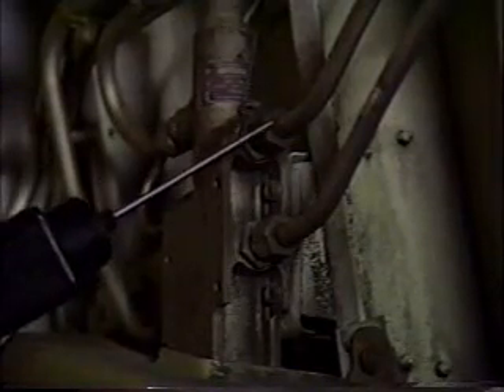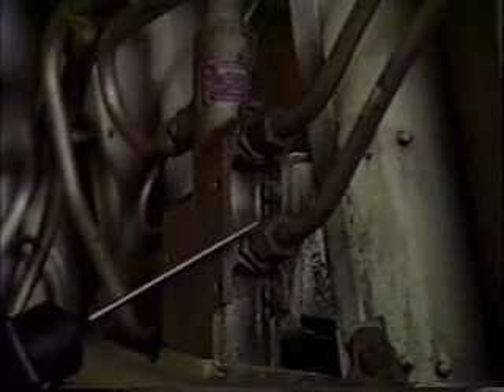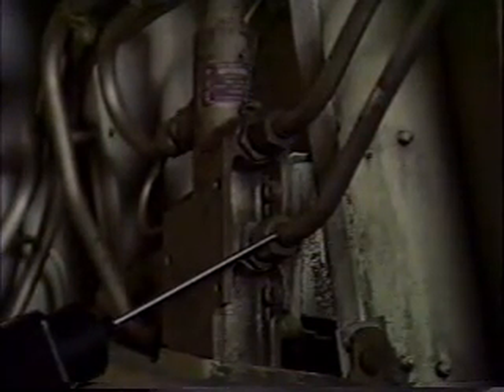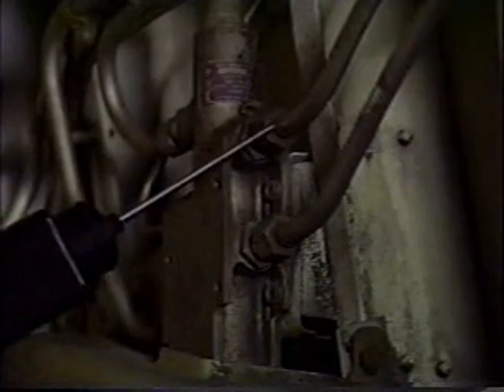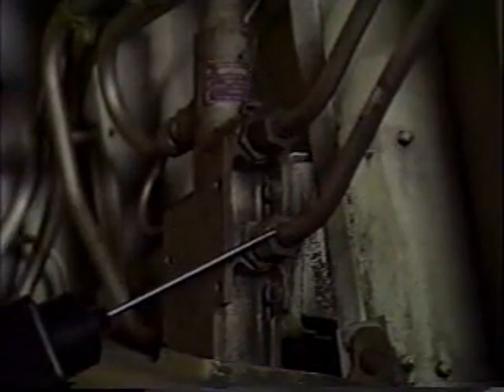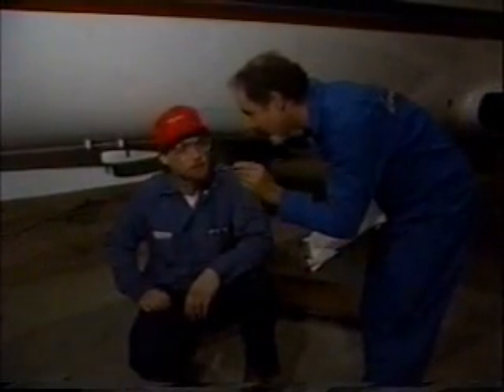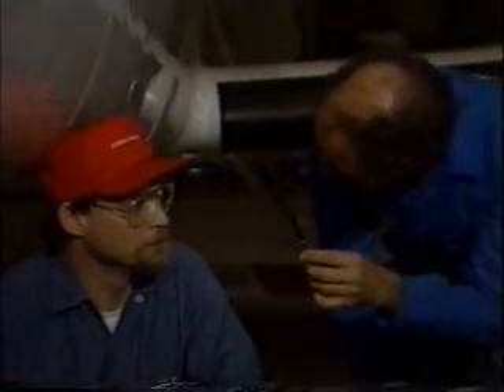Because the sensitivity must be adjusted according to a normal operational valve, a couple of good valves are tested, and a standard is developed. Then the valve is compared to the standard. It's a good idea to maintain a history of the ultrasonic patterns of all key components of your operating equipment to help in diagnosing problems and prevent downtime. Knowing your equipment and understanding how it operates is a critical first step in recognizing changes in its individual sound character or sonic signature.